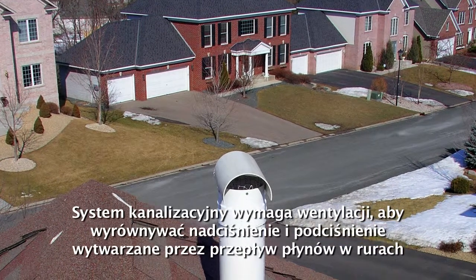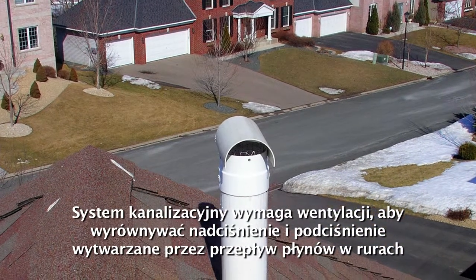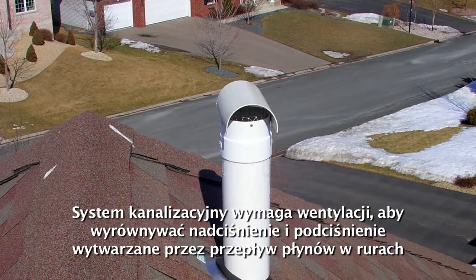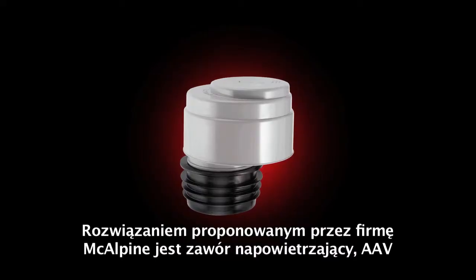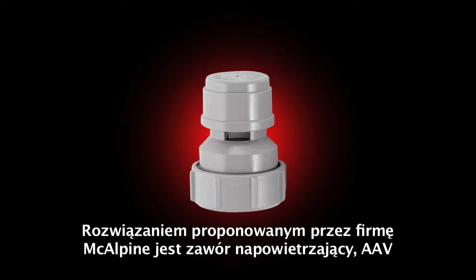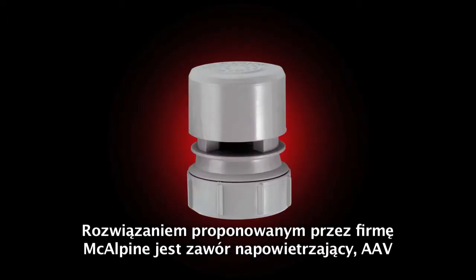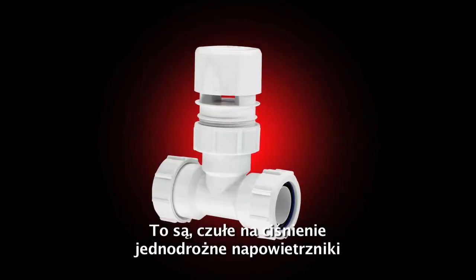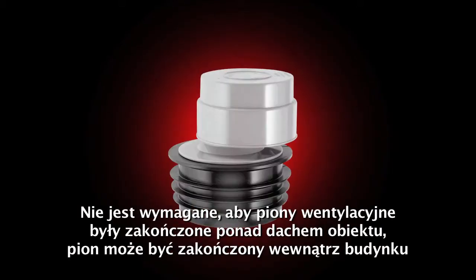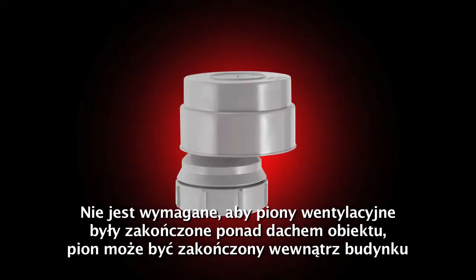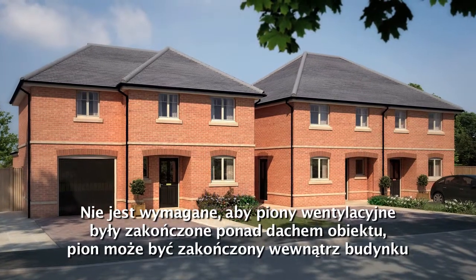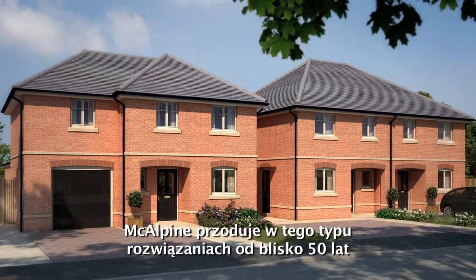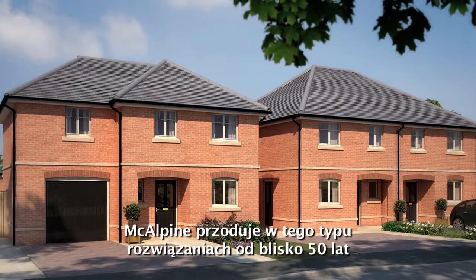Plumbing waste pipework needs to be ventilated to relieve positive and negative pressures created by the flow of liquids through the pipes. McAlpine's solution to plumbing ventilation is the Air Admittance Valve, or AAV. These are pressure-sensitive one-way mechanical vents. They eliminate the requirement to terminate the vent stack above the roof, meaning the pipe can be terminated inside the building.